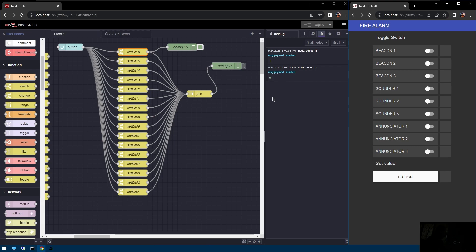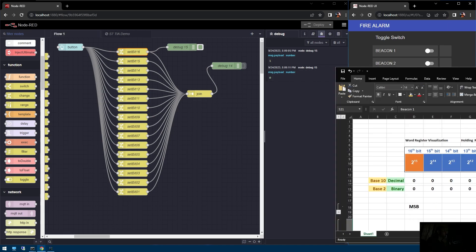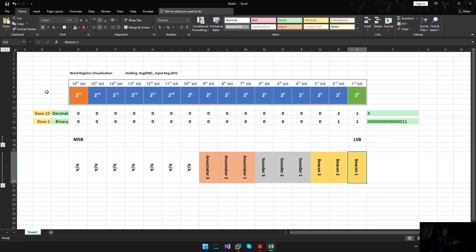What is this implementing in a real application? I had a case on a previous project where equipment uses a 16-bit holding register, and each bit of that register is assigned to a specific function. For example, the first bit here is assigned to Beacon 1 — meaning a device like a beacon is on or off.